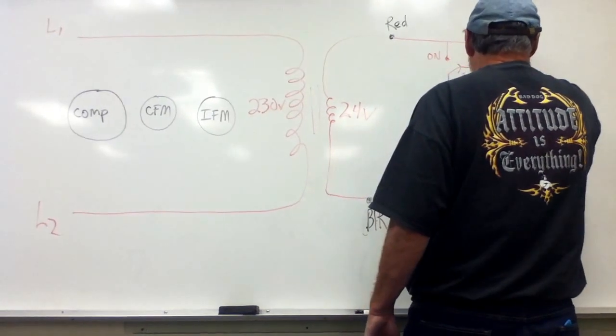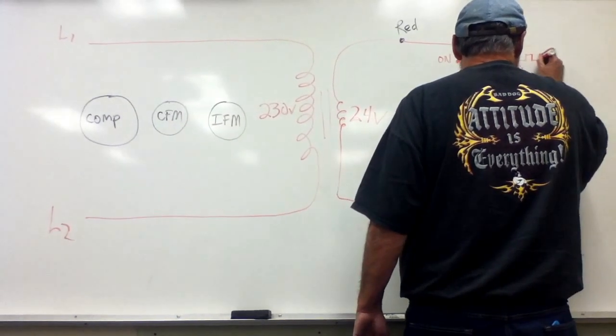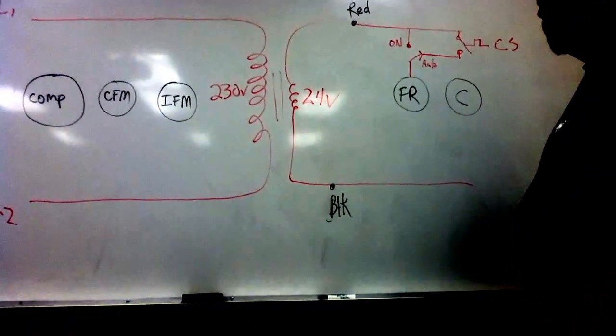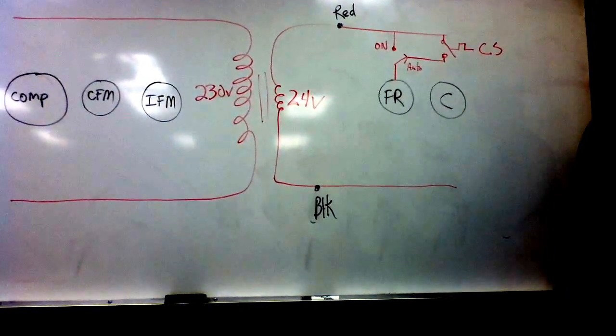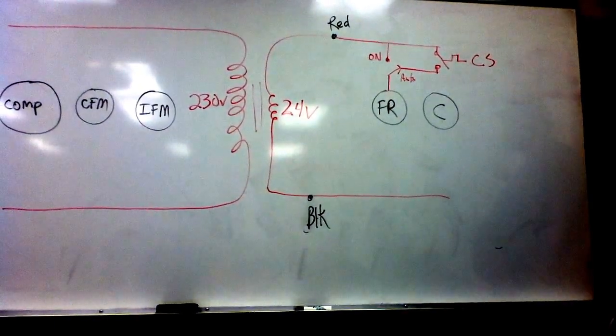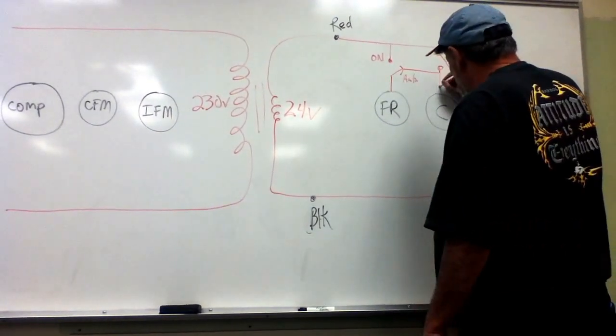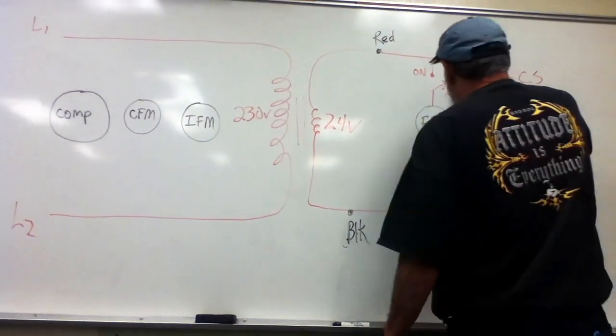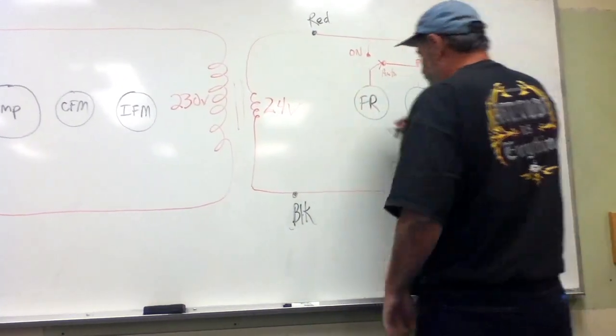We have a thermostat. Thermostat on my drawings is shown as a bi-metal switch. The thermostat is labeled as CS, cooling stat. Some people call it CT, some people call it TC, cooling stat. So you can change the letters but it's got to be drawn properly. The cooling stat turns on the contactor coil, and at the same time power will go over to the selector switch and turn on the fan relay coil.